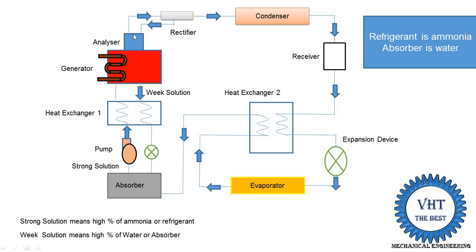To avoid choking of the refrigerant flow in the expansion valve, we provide two components: the analyzer and the rectifier. The analyzer contains different trays of water, so the water vapor is separated inside the analyzer and the water particles return back to the generator. The rectifier further performs the same function — it also separates the remaining water vapor particles not separated in the analyzer, and this water is again supplied back to the generator.